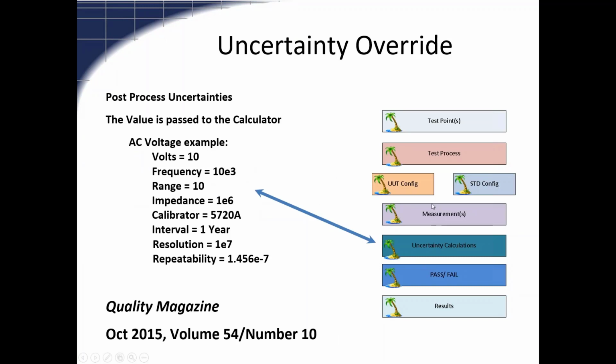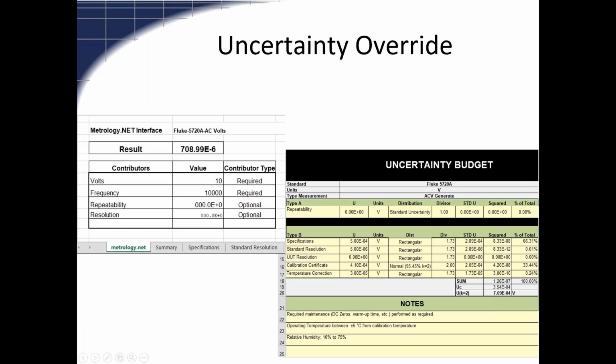After I do my measurement, I post that up. I'm going to take those values and send them into my uncertainty calculator, which is going to run that calculation. And we do that here with a spreadsheet where we put in our inputs. We wire up through some fancy Excelology to where our uncertainties are going to be calculated in something our accreditation body is used to seeing.